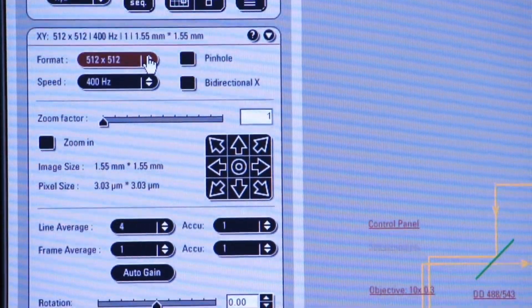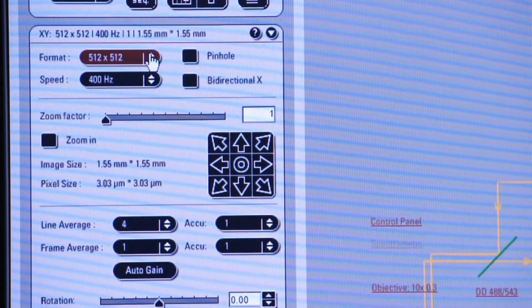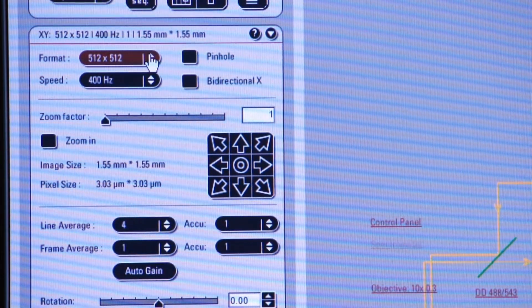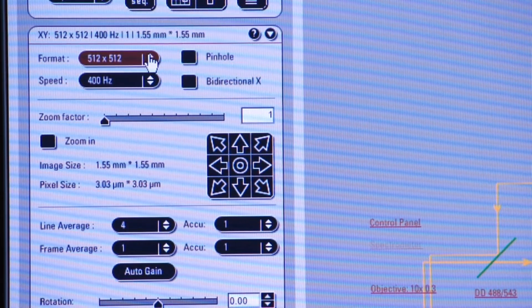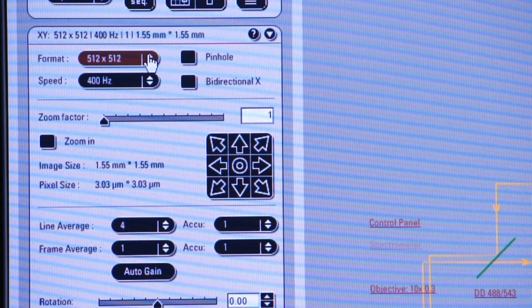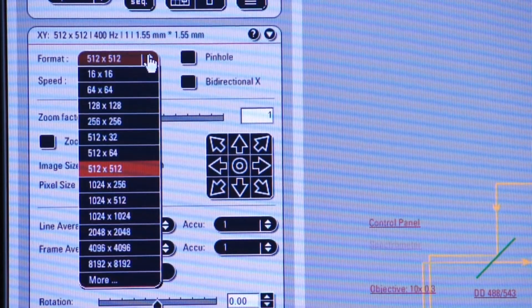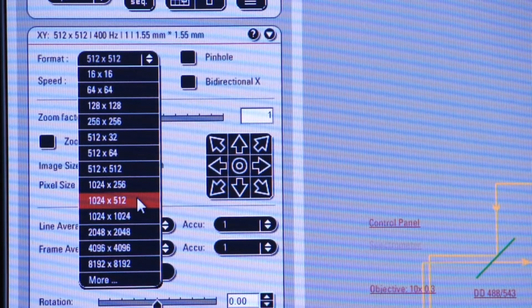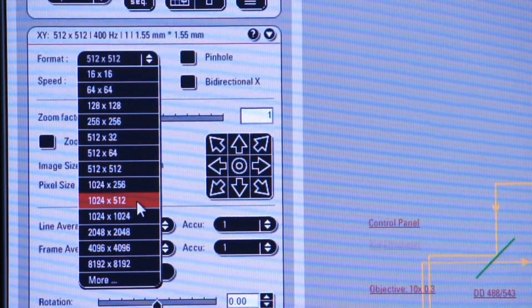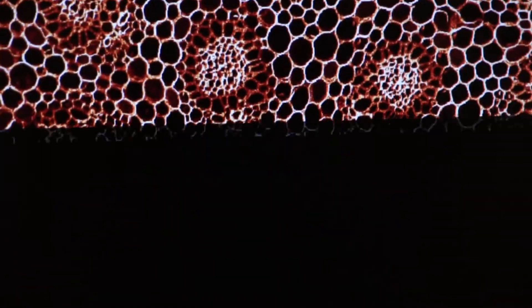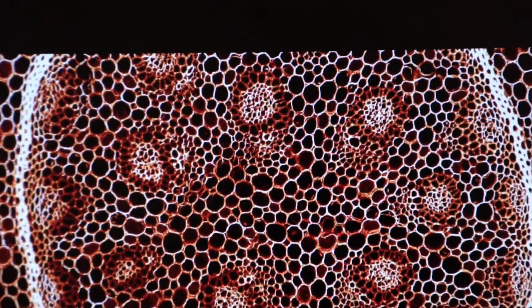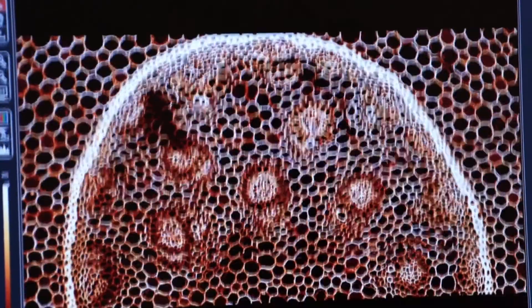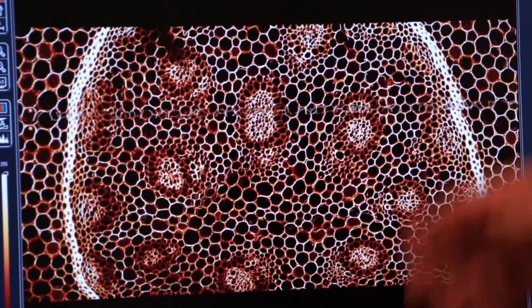One feature that's very useful when I'm using a specimen with a fluorophore that quenches or photobleaches very rapidly is I can select a narrow, long window of resolution. So if I select 1024 by 512 and I go live, I now see on my resultant image a narrow window of high resolution. This makes it easy for me to reposition my image using the XY stage and so the refresh rate is a little bit faster.